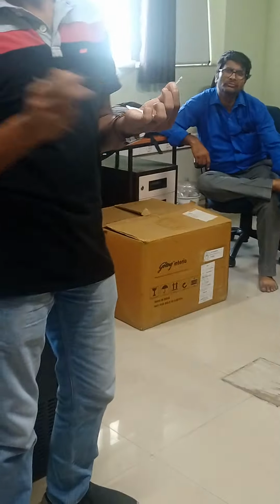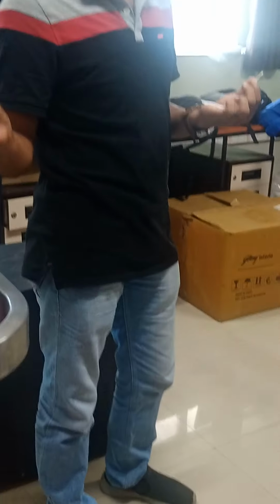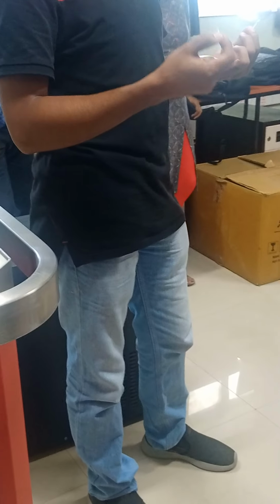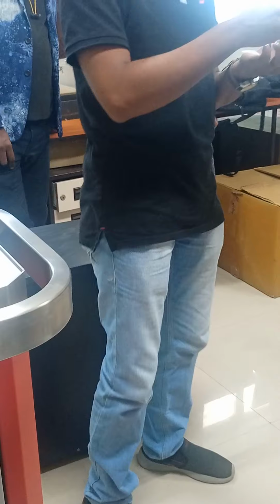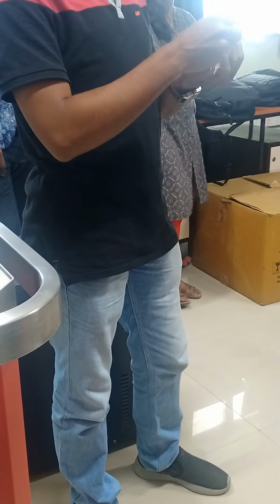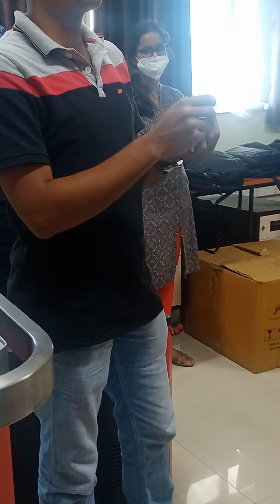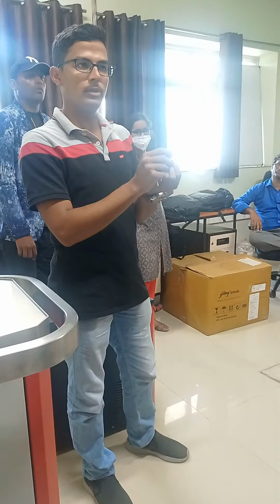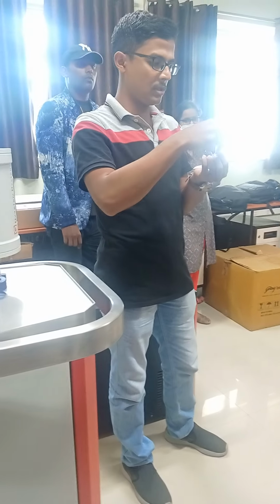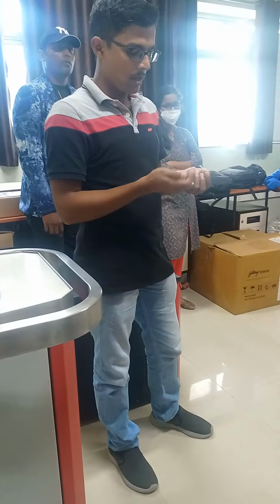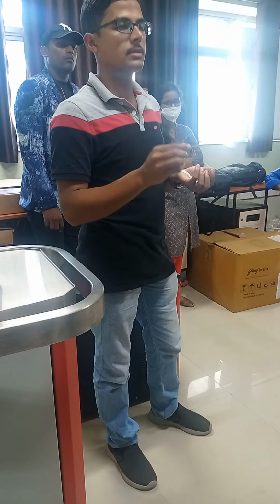Why? Because within the VSM, the sample will vibrate with a frequency of 40 Hz, so there is a chance of the sample coming out from the capsule. That's why the sample is wrapped with the Teflon tape first. Then we place it within one capsule, and another capsule is used for safety purposes. And this is the brass sample holder.